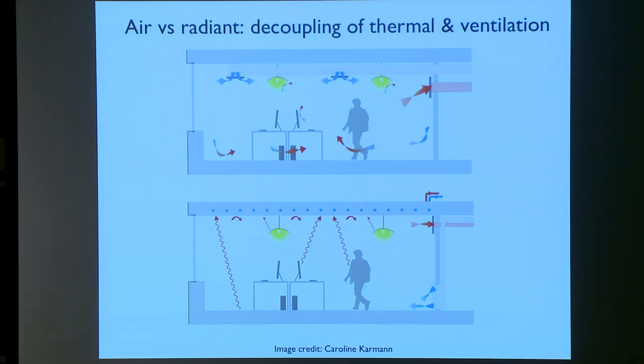So air and radiant systems operate fundamentally differently in terms of how they extract heat from buildings, their total cooling rates, their rate of cooling, and the temperatures they maintain. Air systems are controlled mainly from air temperature, while radiant systems are controlled more from operative temperature.